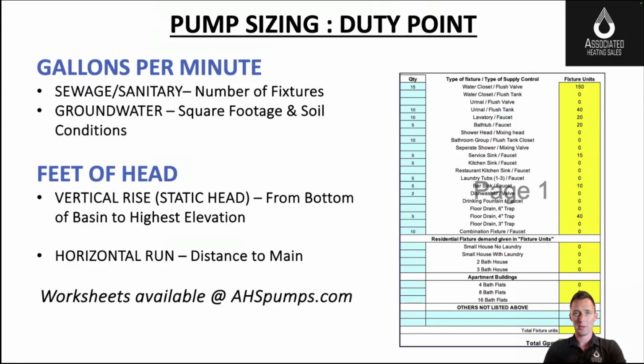First part of your duty point is how much flow do you want the pump to do? In sewage pumps, that's based on the number of fixtures that are feeding into the pit. I have a nice worksheet, but you get a fixture unit count. And again, each pump is doing the full flow.